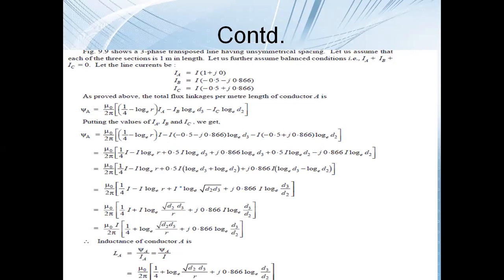To equalize that voltage drop among the different phases, we need to change the position of the conductor across various intervals, and thereafter the inductance will be equal, so that we finally get the equal voltage drop at the receiving end. The voltages will remain the same. That was what we discussed in the last class.